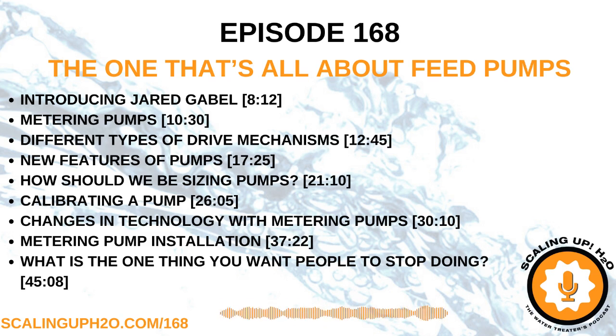Awesome. There are other manufacturers that will have a grayed out line, I believe below 20%, on their stroke. And basically they're saying that we can't say for the accuracy anything below this. Is it safe to say that if you're in that range, you probably need to get a smaller pump?